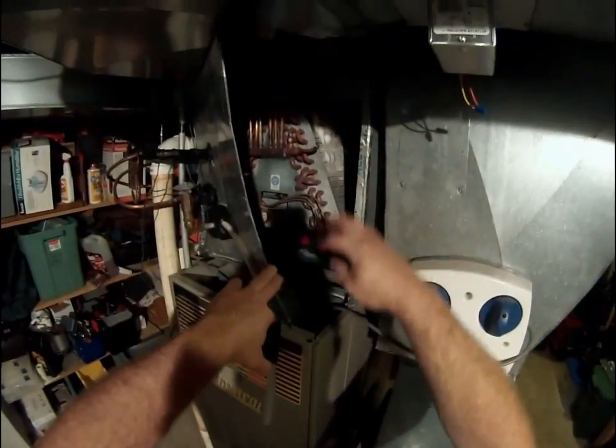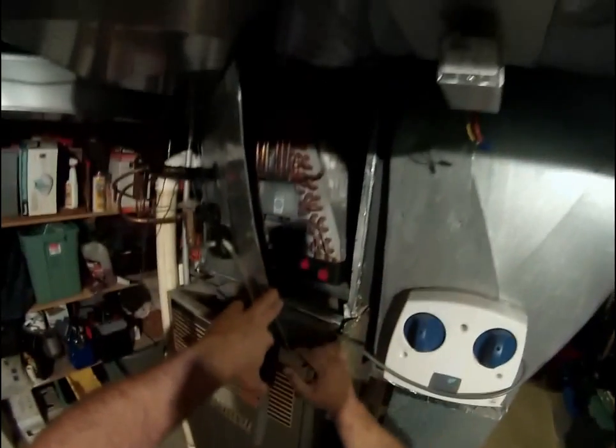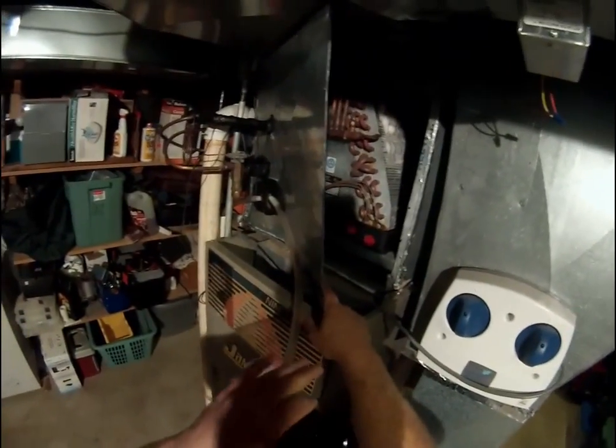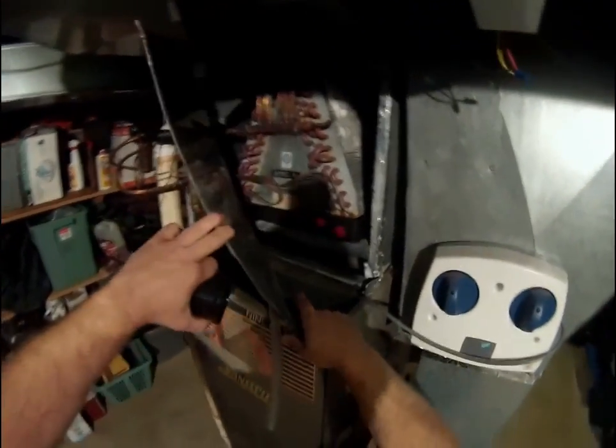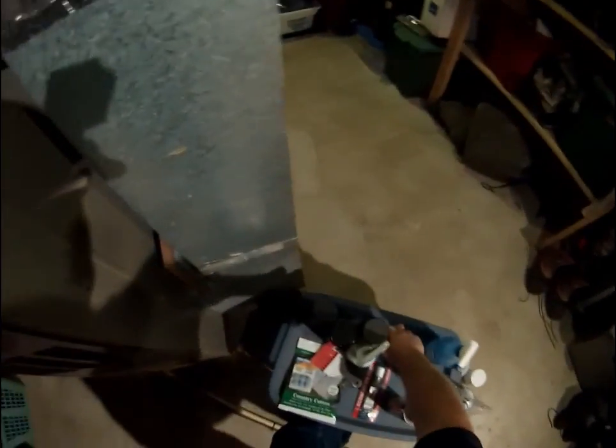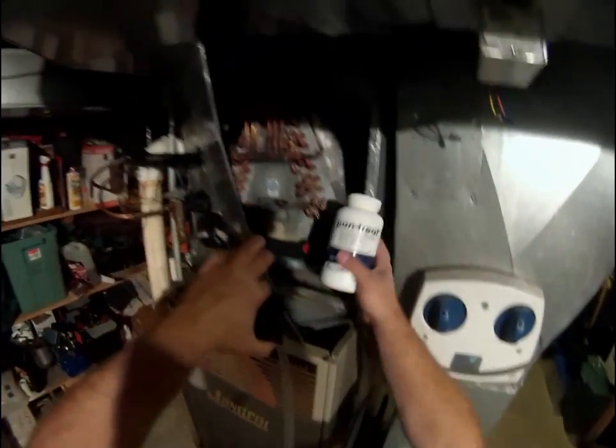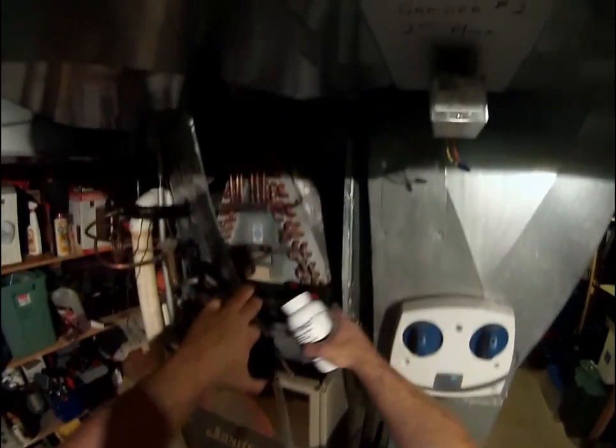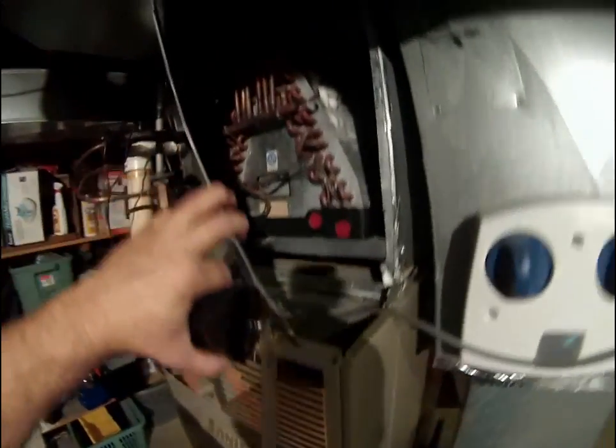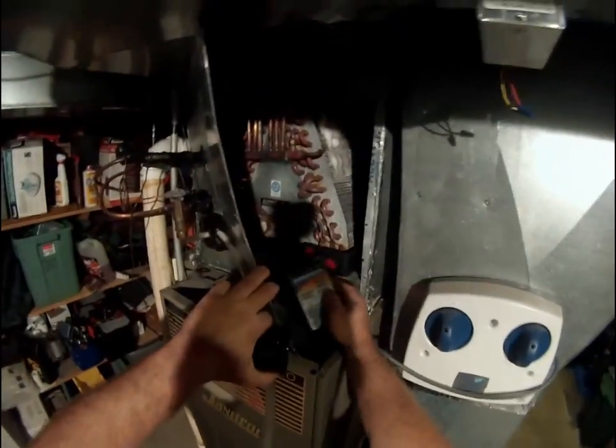Once you start the air conditioner, the condensate will run, and it'll rinse all that dust and dirt right off of there. You just got to keep checking your drains to make sure that it's continually draining, because a lot of times when you aggravate that dirt, it'll block up the coil as well. Another thing you can do when you open this up, a lot of our kits include condensate pan treatment tablets. You drop those in the drip pan here, to keep things from getting all slimed up and keeps them going. Some of them are smaller kits, just a 6-pack. This bigger one is a 200 pack in our deluxe kit.